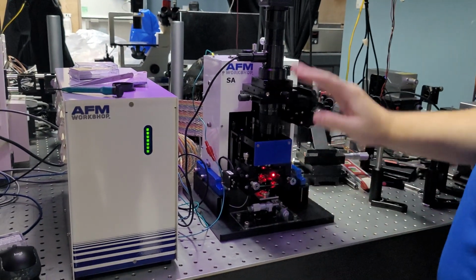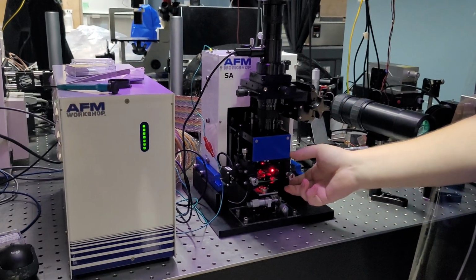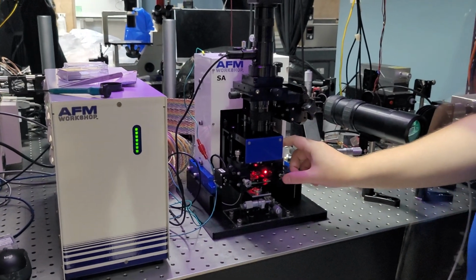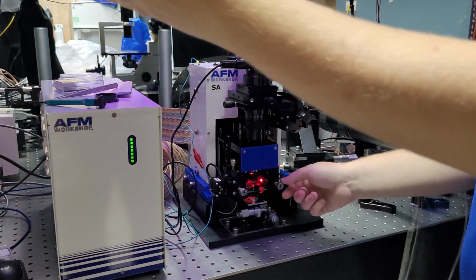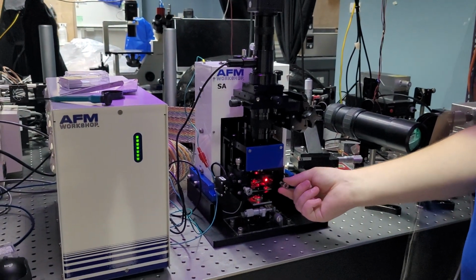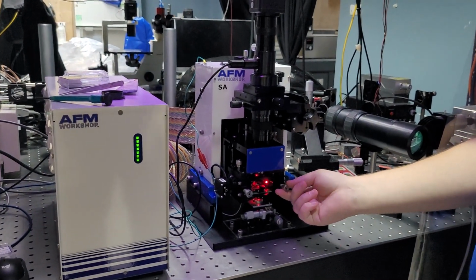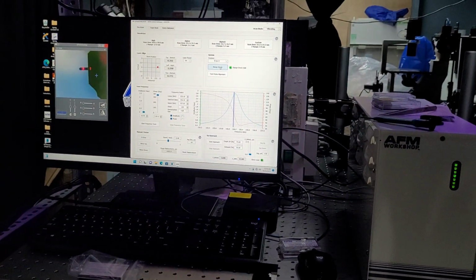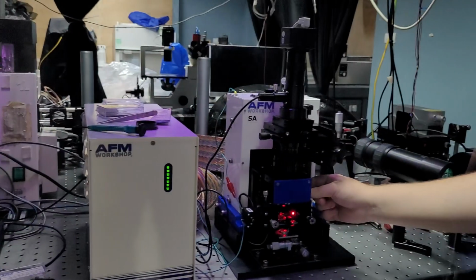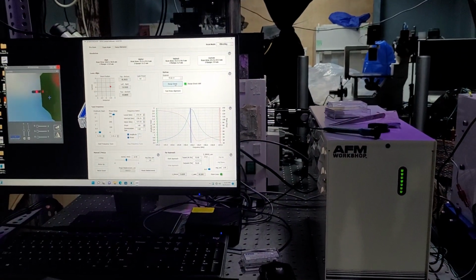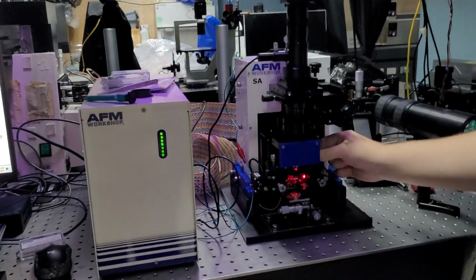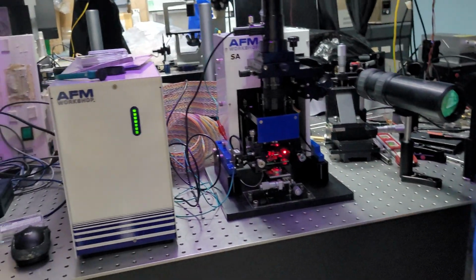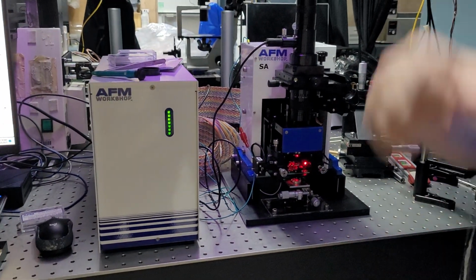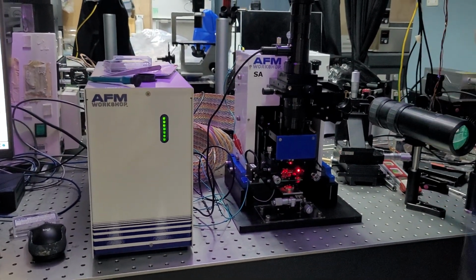So going on further down, like I said, this is the light lever. On the right side, you have your laser controls. Now that we have our cantilever in and we're focused on it, if I go ahead and turn this, you'll notice that this moves the laser spot up and down within the software. And if I move the top one, it moves left and right. So we should reposition. Where should we position the laser? So the laser is going to be independent of this.